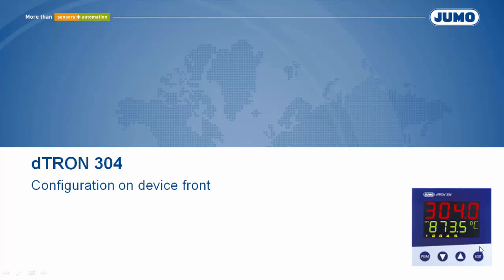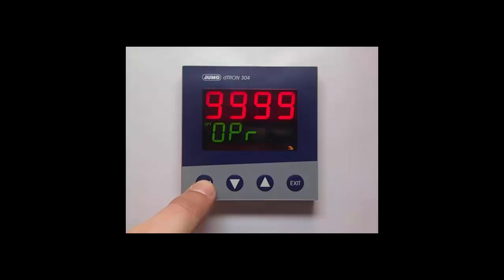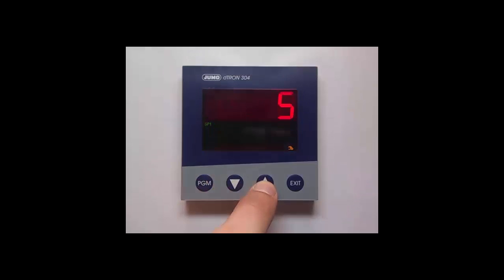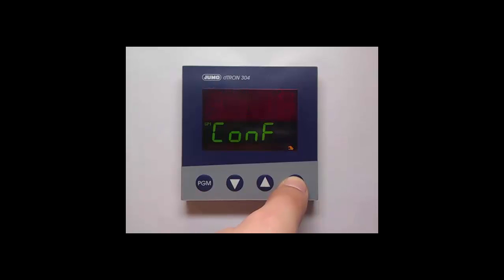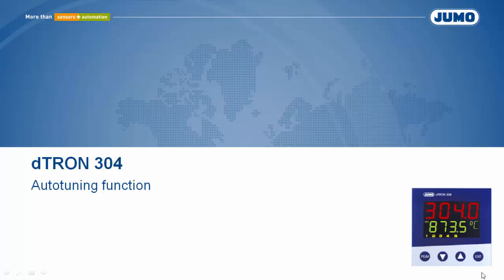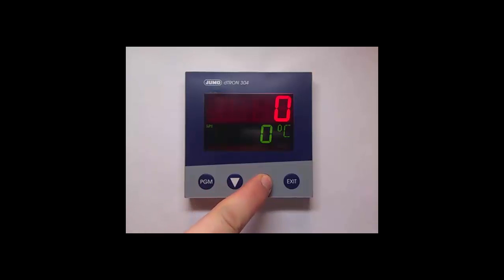Subsequently, the configuration is shown via the device front. The settings are made in the menu Inputs of the configuration level. The signal for input 1 is a 4 to 20 mA signal, and shows linear behavior. 20 mA represents a temperature of 200 centigrades. The configuration of the controller is done. After definition of an exemplary set point of 150 centigrades, the controller heats until 150 centigrades has been reached.